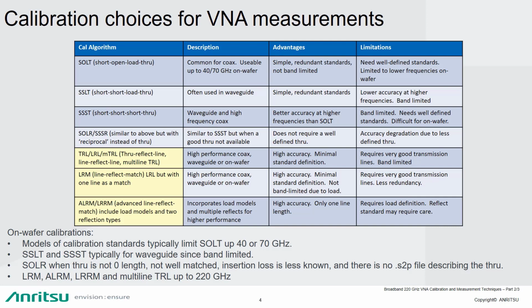So now we want to start taking a look at the calibration choices that we have for on-wafer measurements. This would apply for any on-wafer measurements, so whether it's 70 gigahertz or 110 or 220, some of these aspects will still apply. And one that many are already familiar with is the SOLT, or short open load through calibration. And these are commonly used up to 40 and 70 gigahertz, and they need well-defined standards, and therefore usually are not used above 70 gigahertz because of the drop-off in performance.